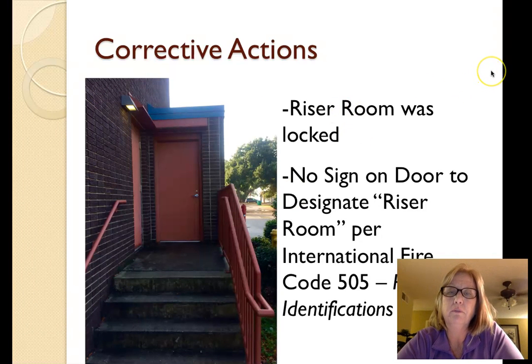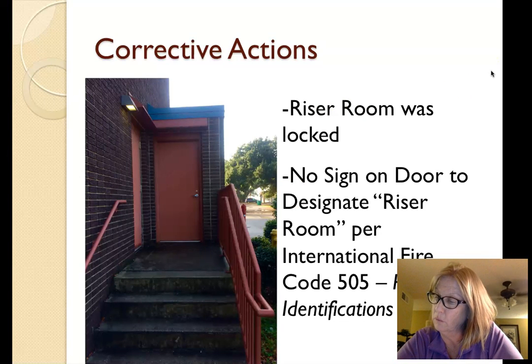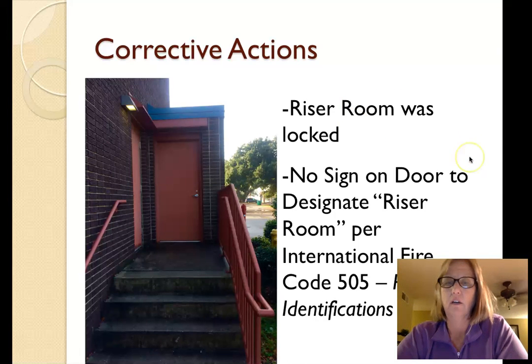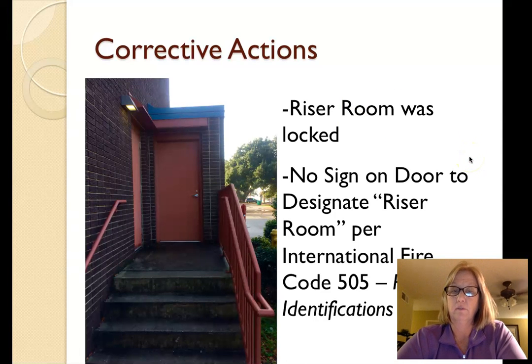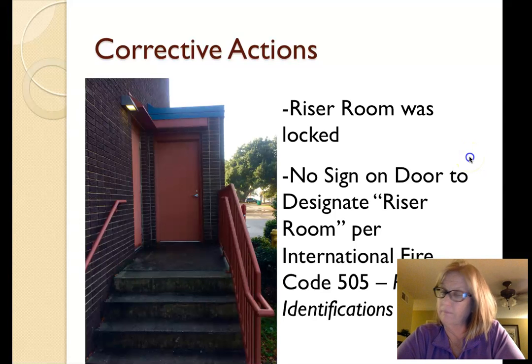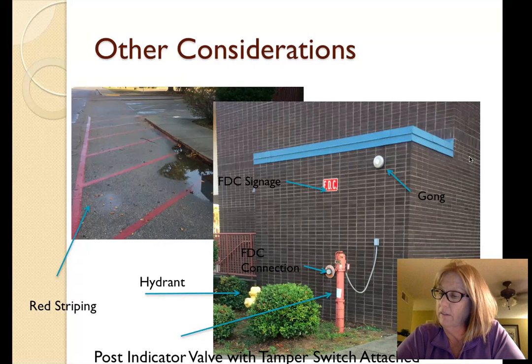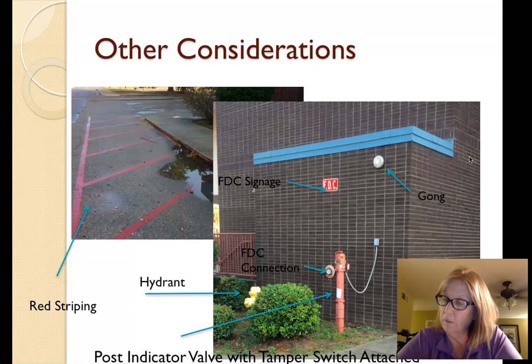We got out to the riser room and it was locked, but unfortunately there was no sign on the door to the riser room, and that is also a violation of the International Fire Code 505, premise identification. On the outside of the riser room, there was a fire hydrant located within 100 feet, a post indicator valve in the open position with a tamper switch connection and a notification gong.